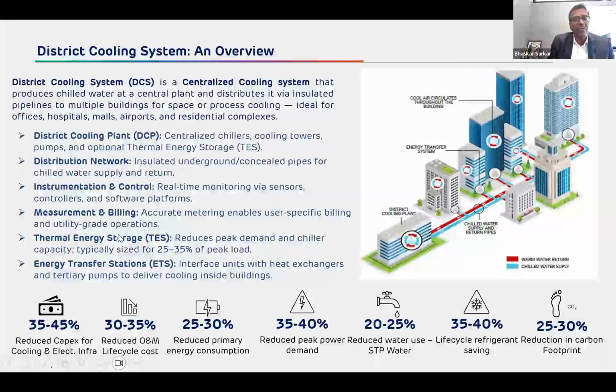And also there is a concept of thermal energy storage, whereby during the off peak or during the TOD, when the TOD tariff is less, the chillers can be used to generate chilled water and top it up in the thermal energy storage tanks, which are like batteries. And when there is a peak demand, at that point we can run fewer chillers, and we can use this chilled water already stored in the thermal energy storage batteries, and that also reduces the number of chillers or the number of units consumed.